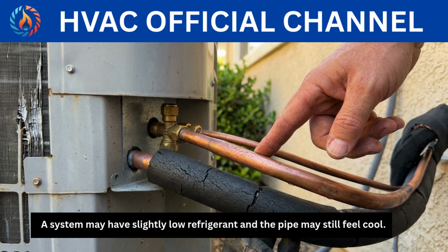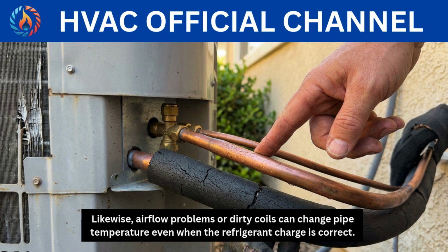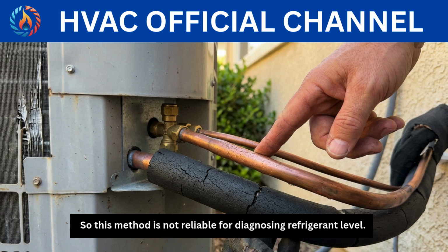A system may have slightly low refrigerant, and the pipe may still feel cool. Likewise, airflow problems or dirty coils can change pipe temperature even when the refrigerant charge is correct. So this method is not reliable for diagnosing refrigerant level.